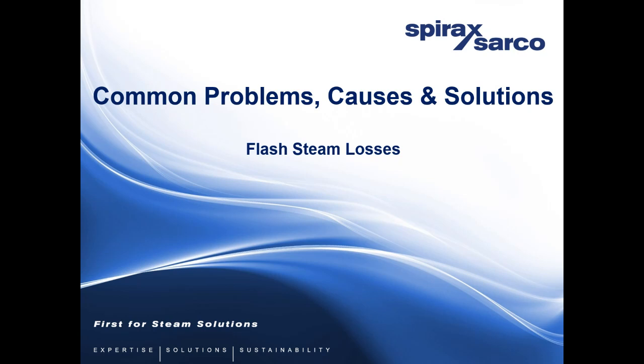But if you've got a justification because you are in the pharmaceutical industry or the food and beverage industry, there is the argument to be made that steam is then becoming an ingredient in the products you're selling. So if you're cooking via steam injection, for instance, steam is an ingredient. It's entering the product. So there is a strong argument for the use of clean steam generators. I know that goes on a slight tangent, but that's a different system which allows you to use less water because it's sealed to a certain degree. Again, wherever you see steam come into contact with product, you're going to see loss because you can't recover that condensate.